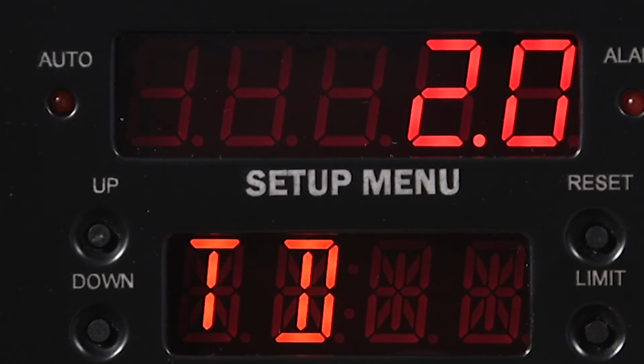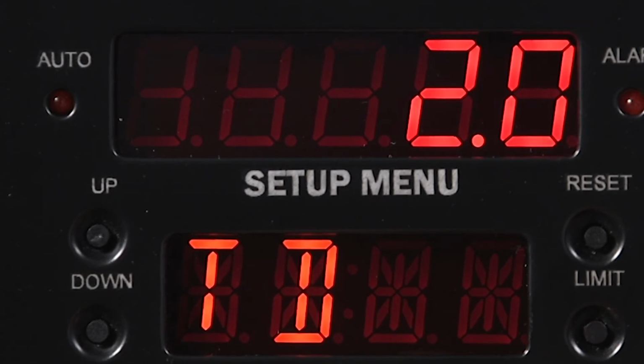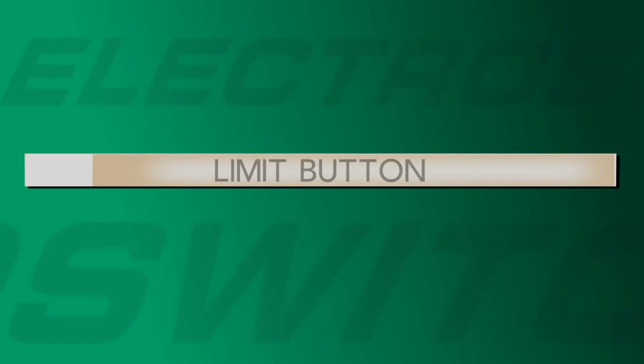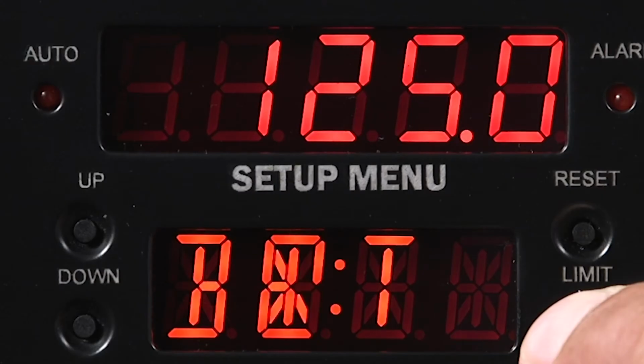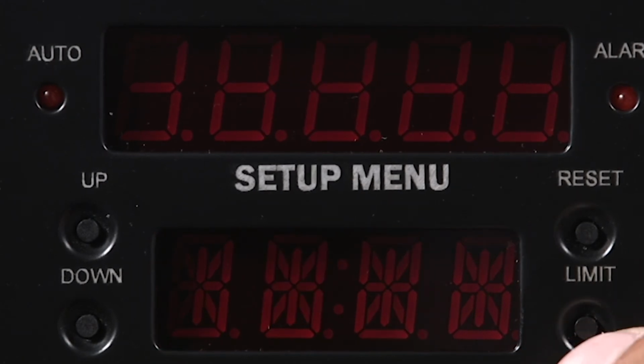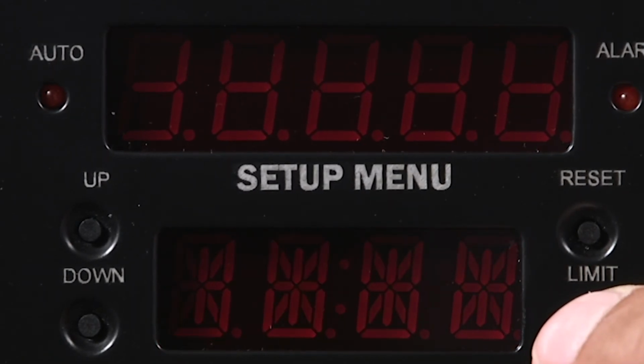Next is a time delay that is available to preclude spurious alarms. It is set at 2 seconds for right now and can go up to 60 seconds. So those are the basic displays. Next, by depressing and maintaining the limit button, we switch the display screen to view the various limit point settings for the battery monitor.